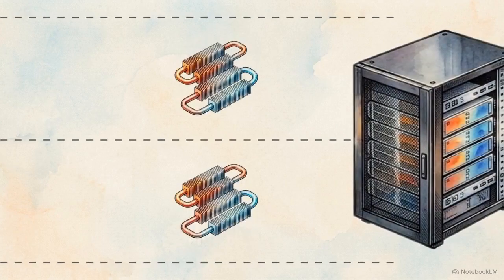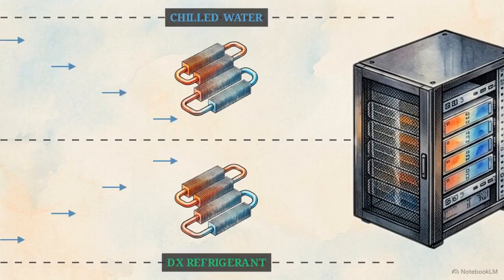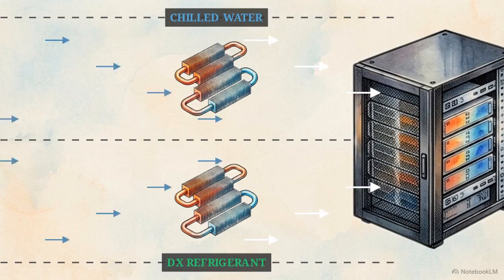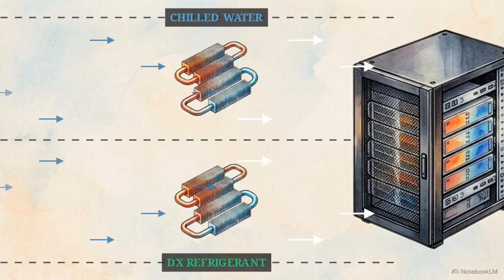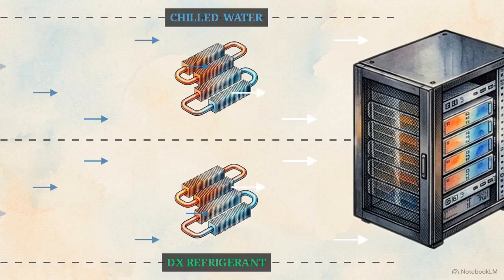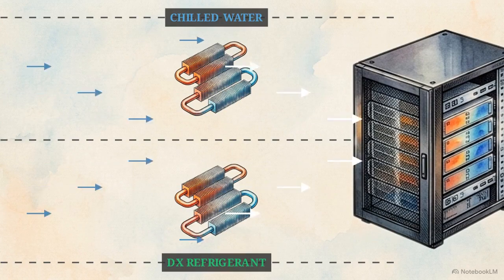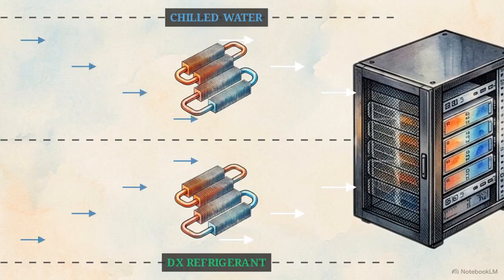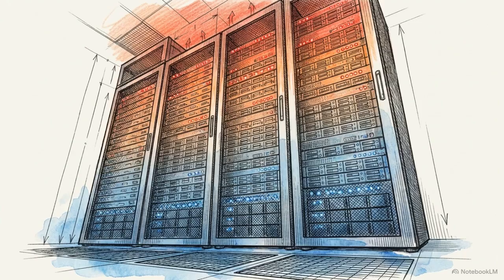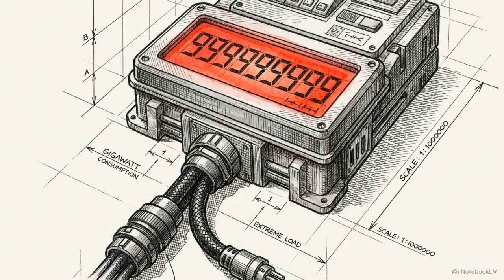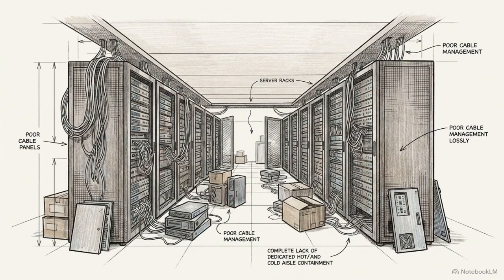These machines push air over coils cooled by large chilled water systems, or direct expansion systems, known as DX, which use chemical refrigerants to pull heat out of the air before it is blasted toward the servers. This brute force cycle of forcing chilled air in and sucking hot air out keeps the hardware functioning, but it requires staggering amounts of electrical power to keep the massive fans and compressors running. Simply blasting a room full of cold air has a severe engineering flaw.